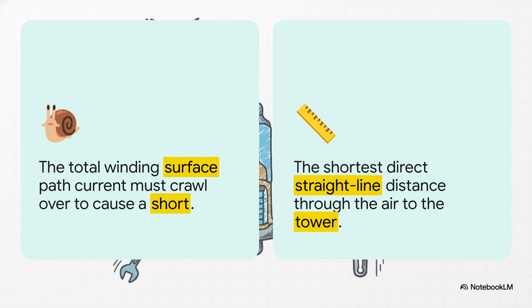To stop these electrical jumps, especially over polluted surfaces, engineers meticulously calculate two different measurements. First is the clearance distance. That's simply the shortest, direct straight line through the air between the highly charged wire and the grounded metal tower. But the real defense is the creepage distance. This is the total surface path the current must literally crawl or creep over to cause a short. Because electricity will follow a wet, dirty surface much more easily than it will jump through dry air, engineers design those umbrella-like shapes to make the creepage distance incredibly long. They force the electricity to take a tortuous, winding path over ridges and under eaves, ensuring the physical surface path is much, much longer than that direct path through the air.